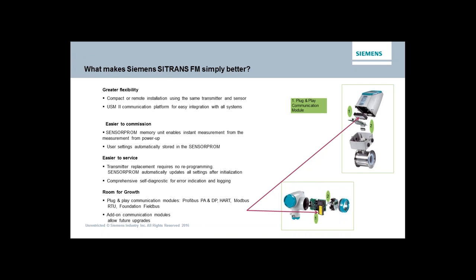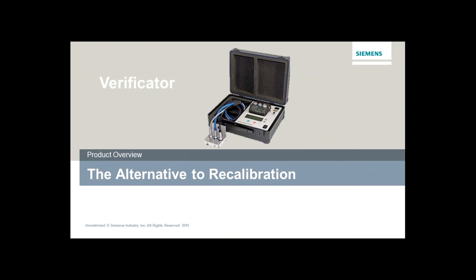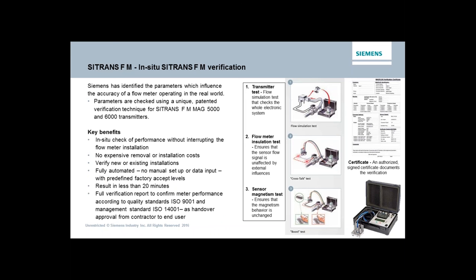The last thing I want to touch on is verification capability — the ability without removing the meter from the process line to confirm the performance of the sensor by reading the sensor prom and measuring how the sensor itself is operating. We check the transmitter for full functionality and also check the interconnecting cable between the two, so at the end of the day you know exactly how your instrument is operating without the need to pull it out of the pipeline or even shut down the process. It's a very flexible design that works with our MAG 5000 and 6000 transmitters.